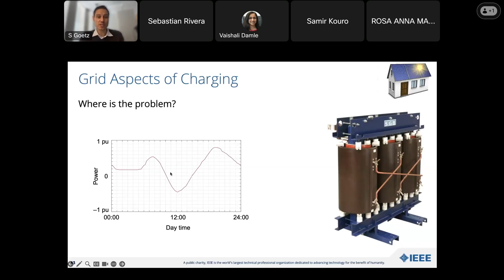When everybody comes home, starts cooking, TV on, and so on. But what changed is this. You see, this transformer has about as much load around noon, but in the opposite direction than it has in the evening peak, because the power is flowing from solar systems back into the medium voltage grid. And what it can lead to in the grid, right here again, high voltage, medium voltage, low voltage, is that you suddenly have power flows that the grid operator did not expect.